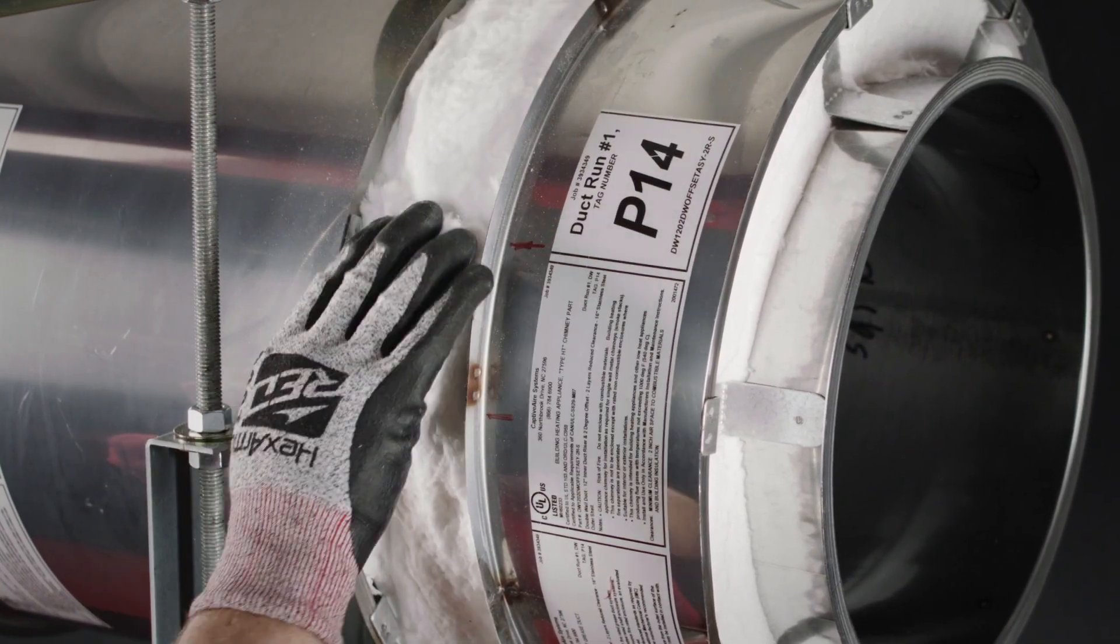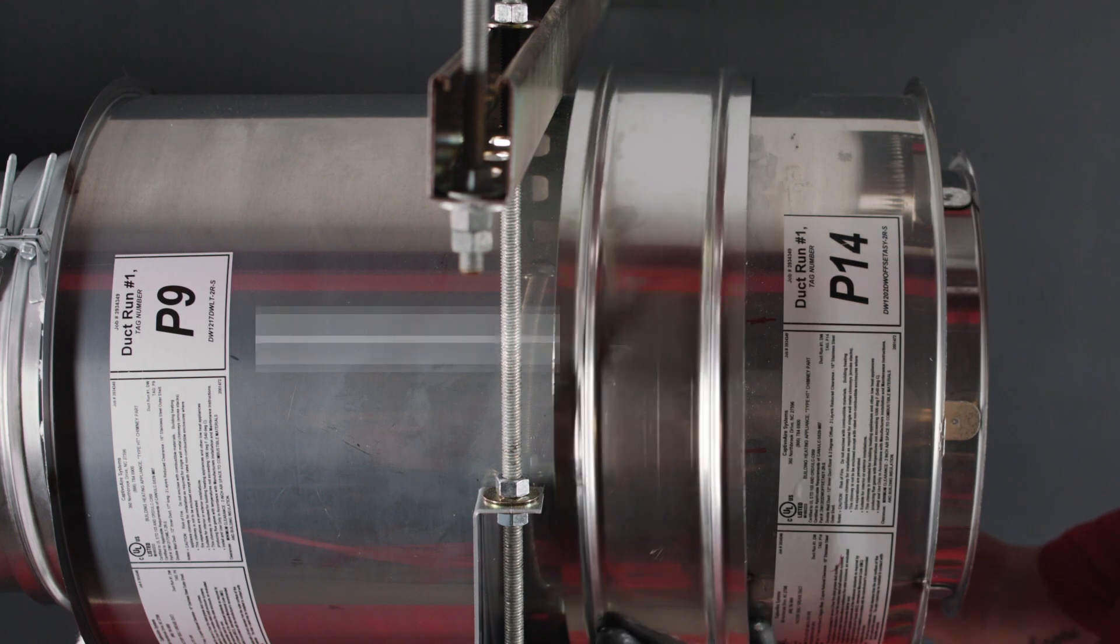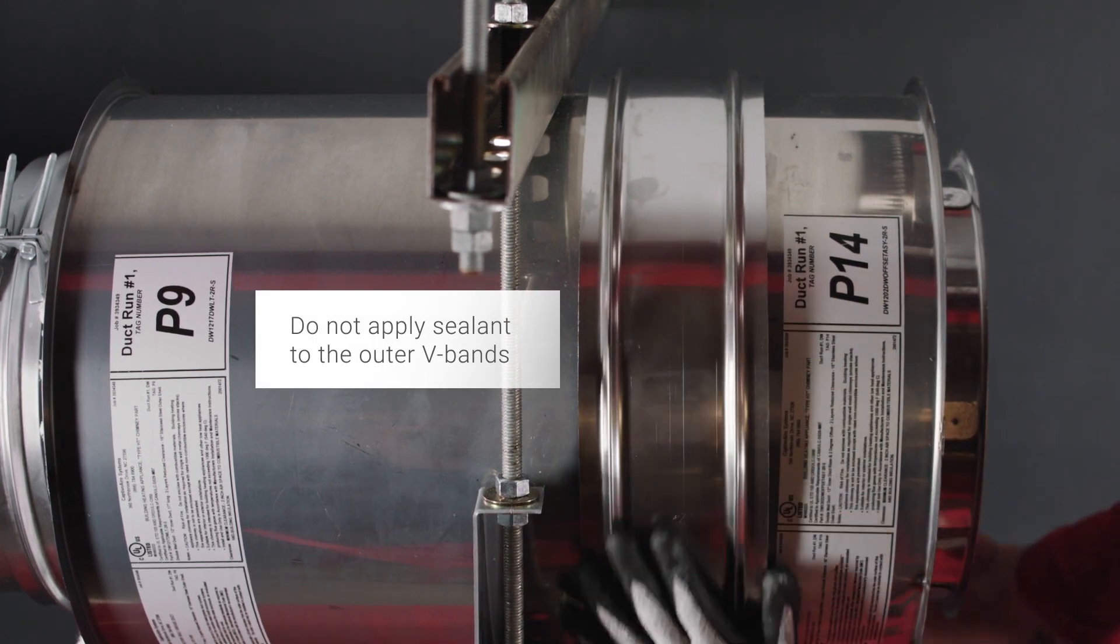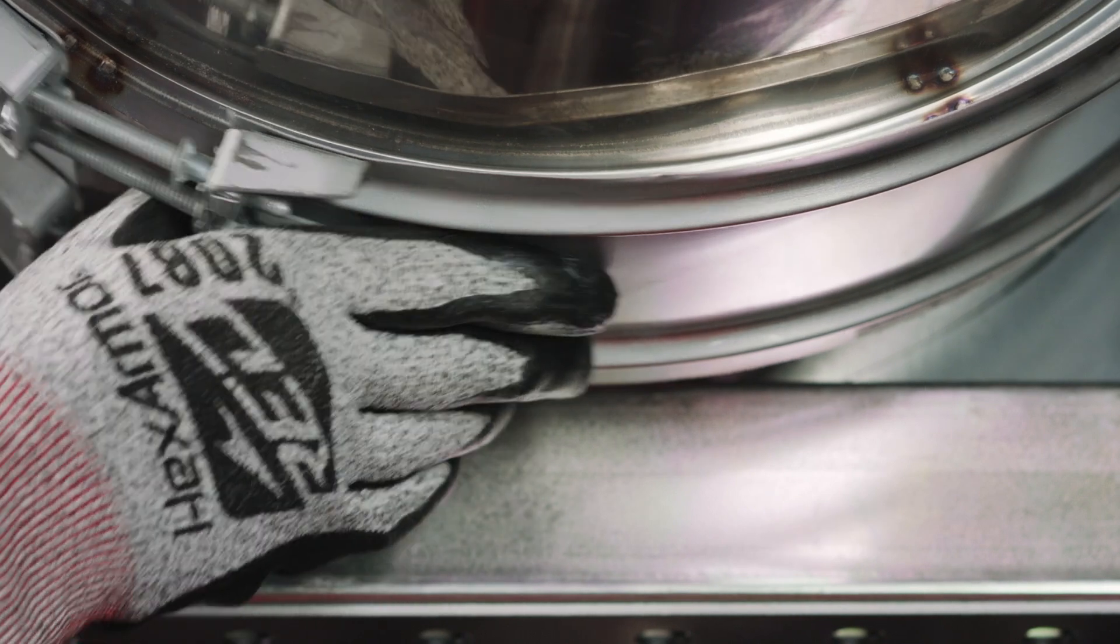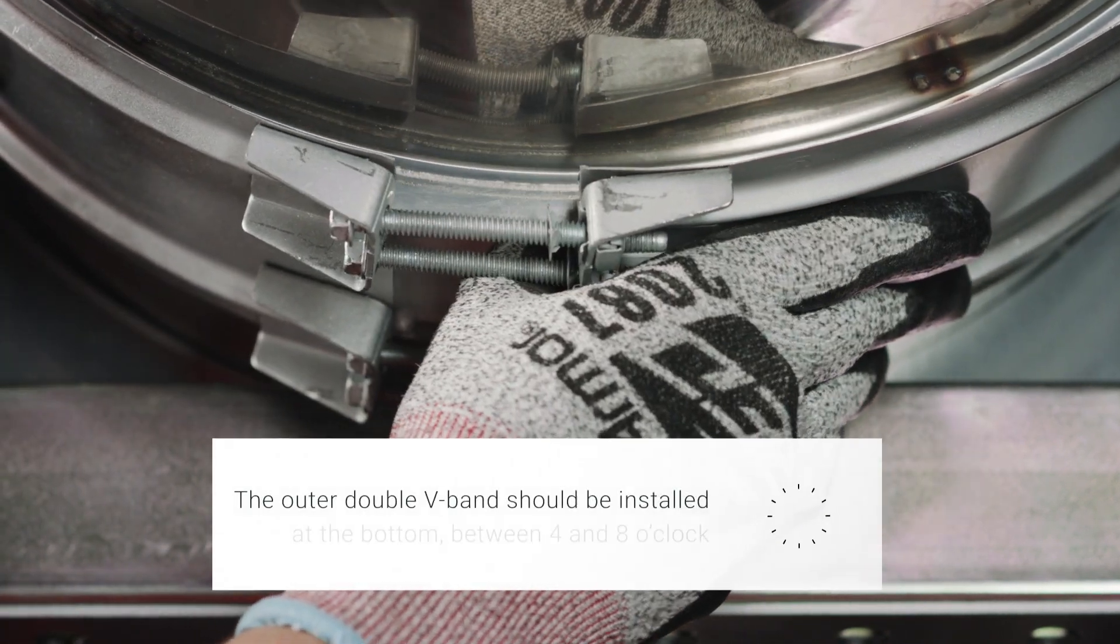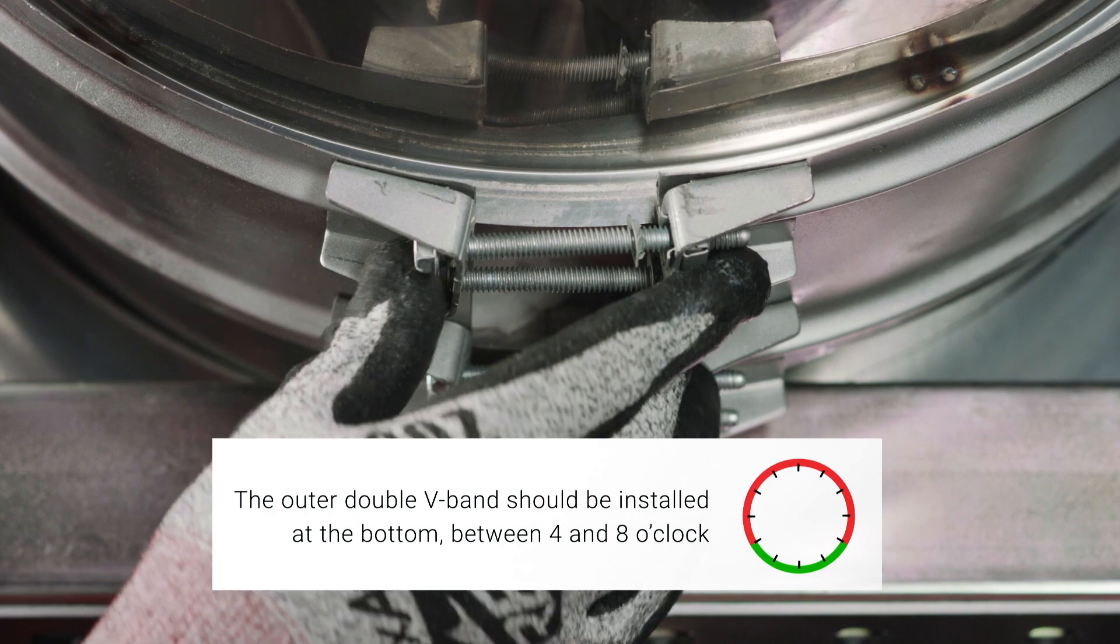Join the two flanged ends of the outer shell by installing the double V-bands. Do not install sealant. When installing ductwork outside, the double V-band must be face down in order to shed rainwater.